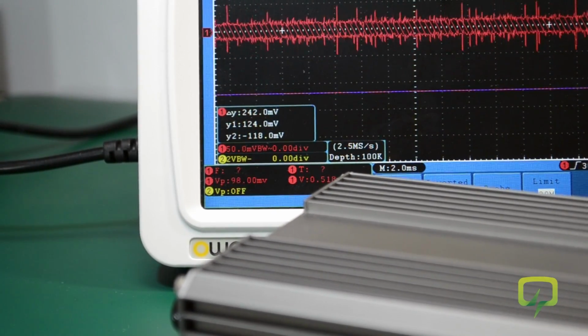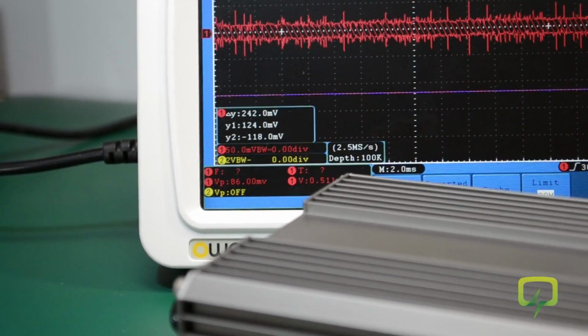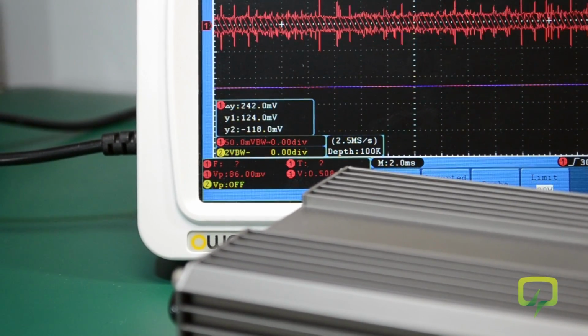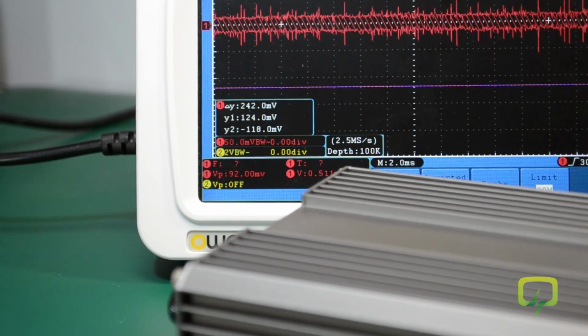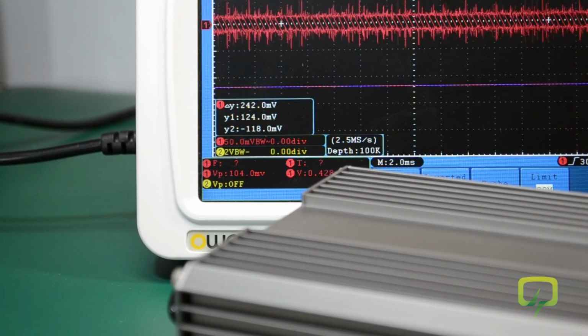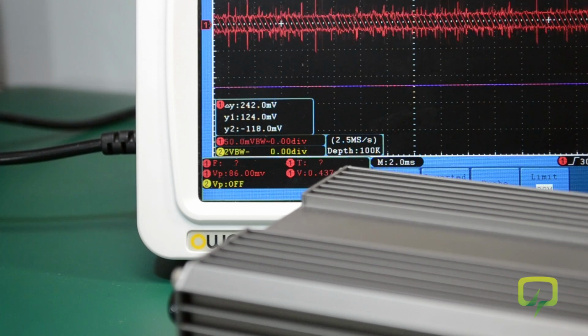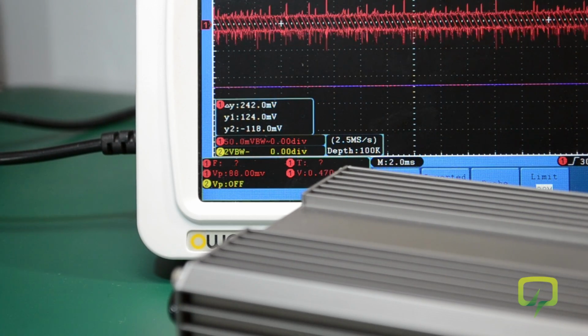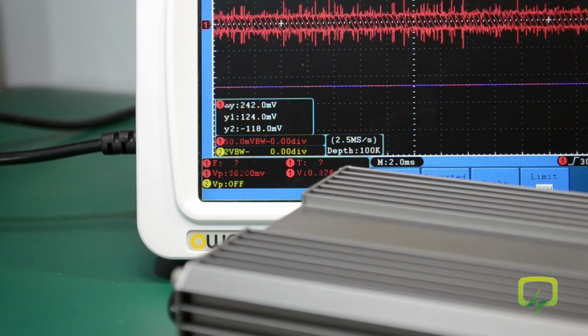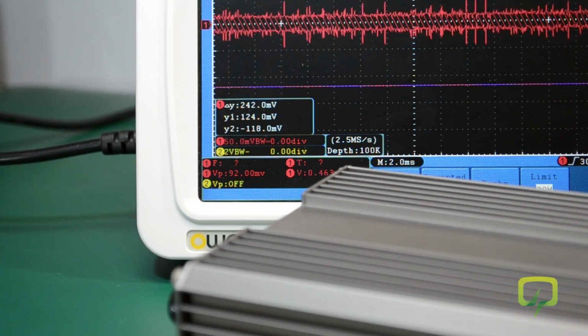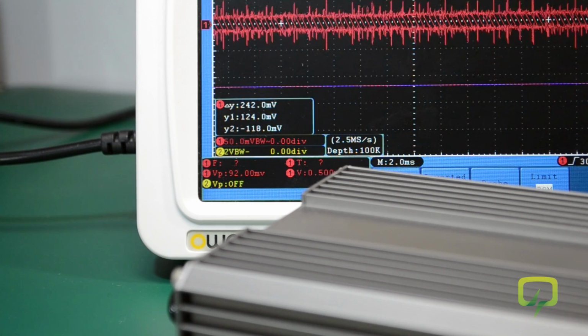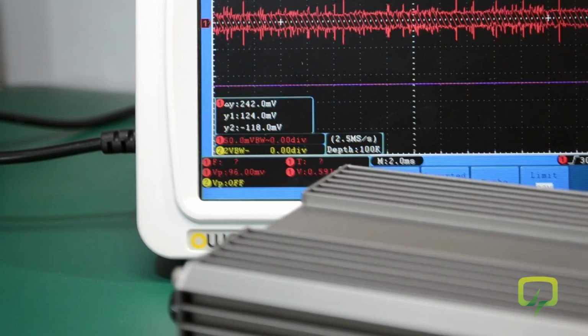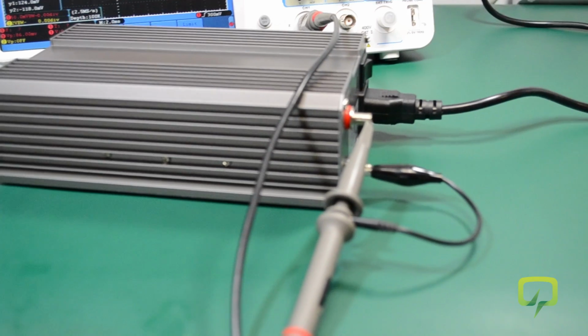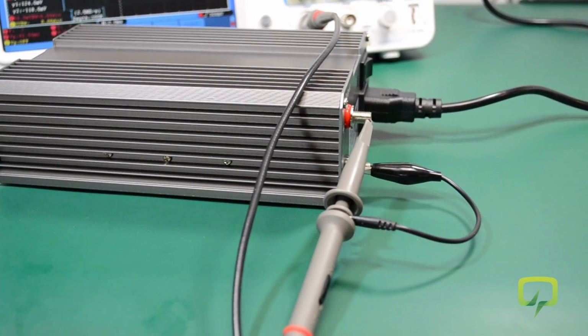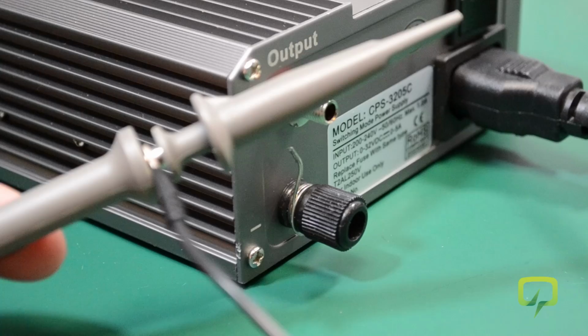You see we're getting 80 to 100 millivolts peak to peak noise, and you might say this power supply is way out of spec because in its spec sheet it should have less than 30 millivolts output noise peak to peak, and we're actually getting close to 100 millivolts. But no, that's not the case. We are actually picking up all sorts of noise from the room because we're using that ground lead from the scope, which is acting as an antenna.